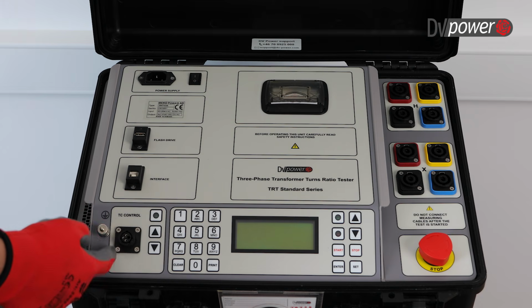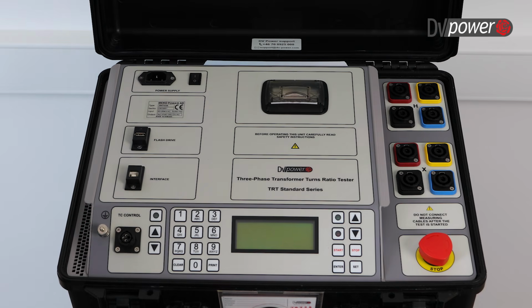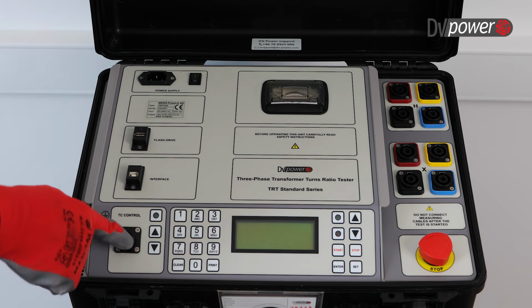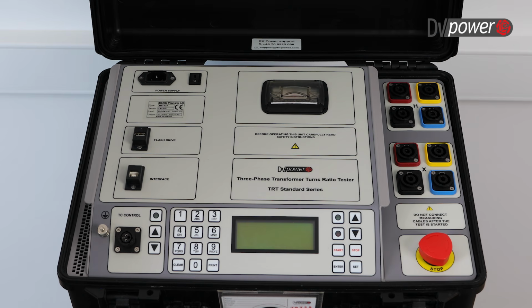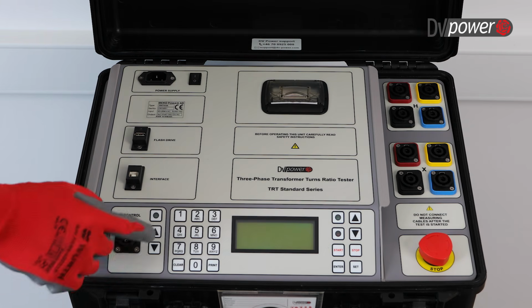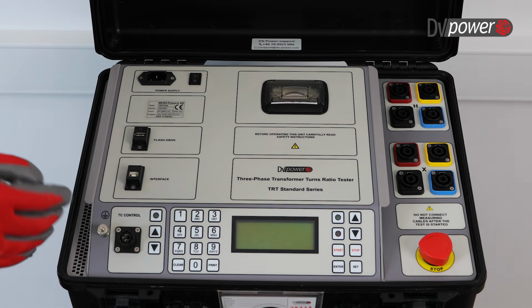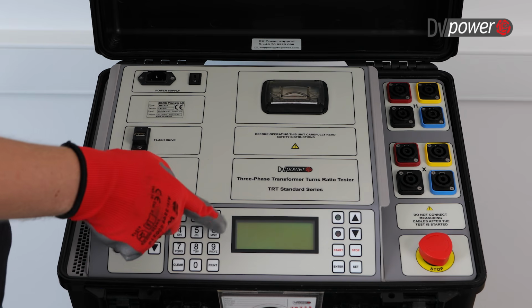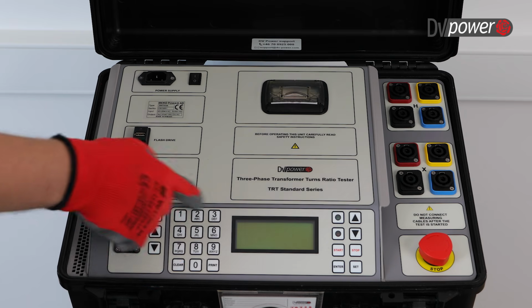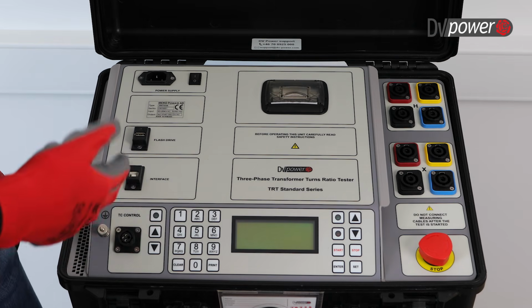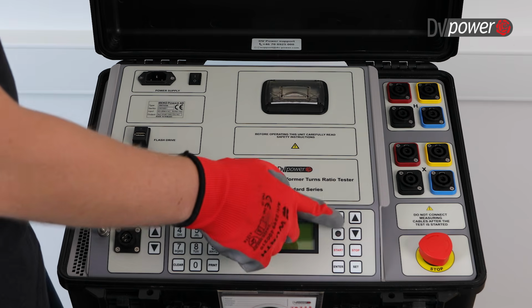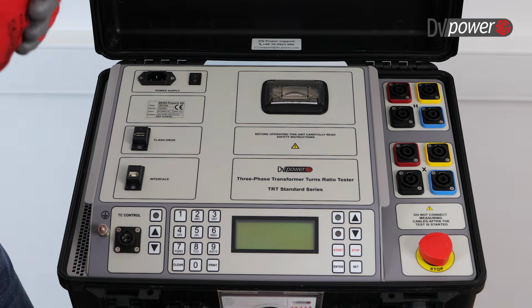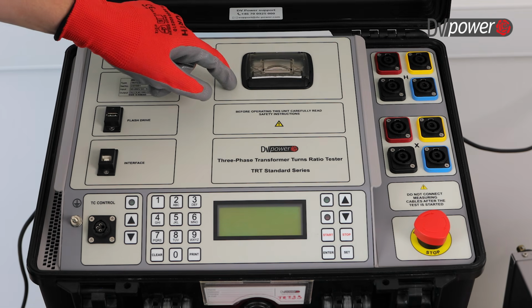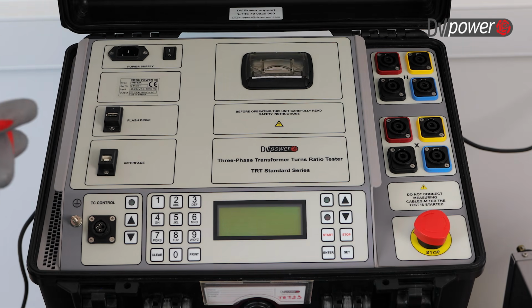This part of the device, called TC control, enables the user to connect the TC control cable to this connector, and the other side of the cable should be connected to the tap changer control box, and therefore we enable the user to change the tap position of the transformer by pressing these arrows. An LCD screen with 4 rows is also there, along with the keyboard, and by this part we can see the results and set up testing parameters. These diodes indicate if the test is running. The built-in printer is an optional feature, so the user can print results when the test is finished.